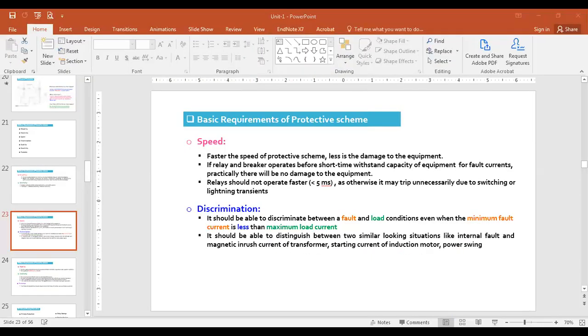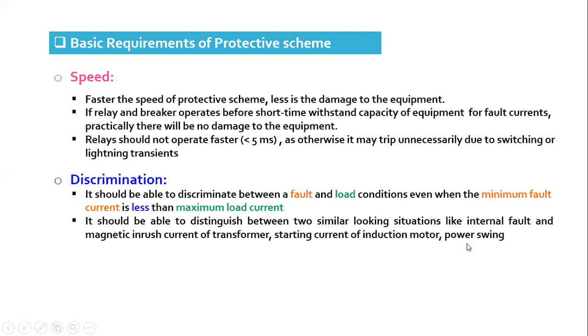Discrimination, we have also discussed. The protective scheme must be able to discriminate between fault and load conditions. Even in the case where fault current is less than normal load current, it is still a fault, because even though there is no significant damage to the system, current is flowing to an undesired path. It should also be able to discriminate between very similar looking situations like fault and starting current of an induction motor, inrush current of a transformer, which is very high, 8 to 10 times the rated current, power swing, and all these conditions. That is what discrimination is.